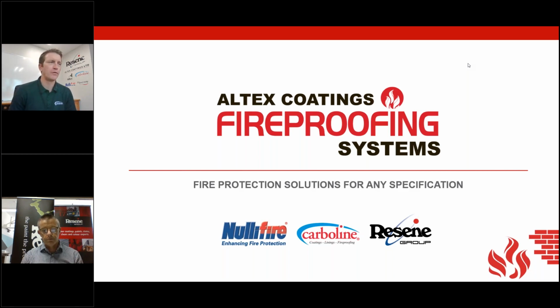So if you do get water damage onto your intumescent film system, particularly one that has been sealed or top coated, you may not be able to visually see that it's been damaged. So for example, the NZICC building where the fire was located, that was up on level 5, the actual area of damage that you got directly from the fire itself and the heat was relatively confined. You probably would have been in the first 20-30 metre radius of that particular burn zone. That's where the damage on the structural steel really occurred.